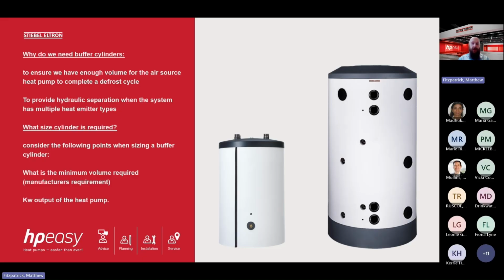It's also there to provide hydraulic separation from different types of heat emitters. It also means you can have multiple heating circuits. For example, our heat pump manager can control 3 to 5 different heating circuits, so 5 different pumps. For that scenario, we would have a buffer cylinder to cover 5 stories of a property.